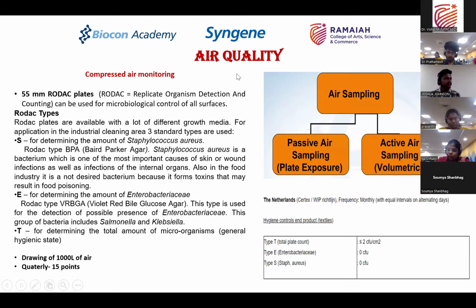So in industries, there are different media plates which are used. The media plates are called Rodac plates. Now, the size of this plate for air sampling is 55 mm. Sometimes 90 mm plates will be used. So depending upon the industry standards, different sizes of the plates will be used. Most of the industries use the 55 mm Rodac plate.